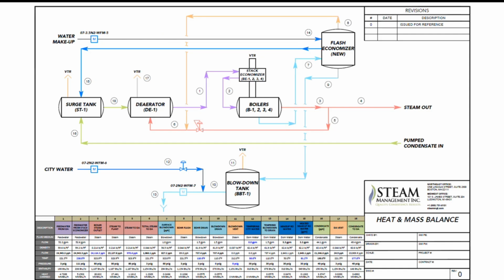The rest of the calculation is going to be done. I could go through all of this, but really the best way to do it is to plug this economizer into your heat and mass balance. And you can see the whole system operating before the blowdown heat recovery and the whole system operating afterwards. All of these calculations are basic thermodynamics, heat transfer, whatever you want to call it. But it's basically heat and mass balance formulas of conservation of energy and mass. So that's how you would come up with the rest of the savings. Once you have that blowdown flow, you're calculating how much flash steam is flashing off, how much heat transfer is going to the makeup water, how much steam that's offsetting downstream. And so it really is just a heat and mass balance type of calculation.